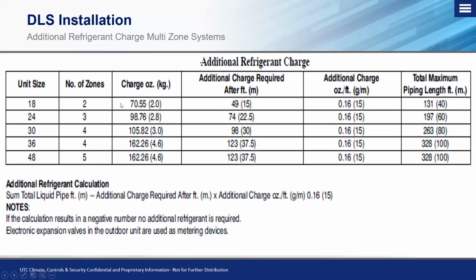So this 49 foot is between both of these zones, not individual zones. So if between both of these zones we have 60 feet, okay, well, we need to take 60 minus 49, and that's how many feet we're over. Multiply that by 0.16, and that will give us our additional ounces that we need to add into the system.